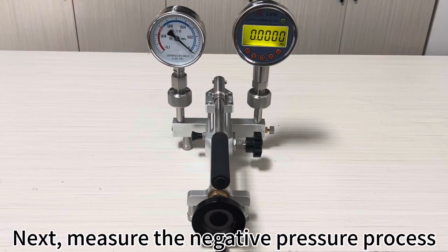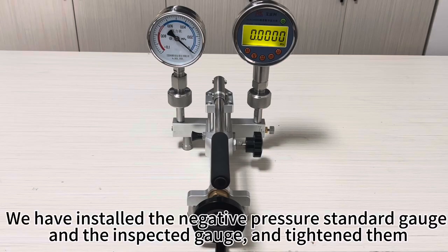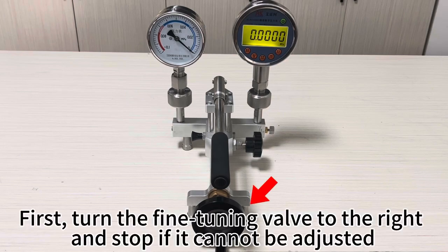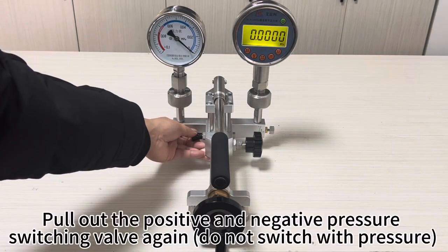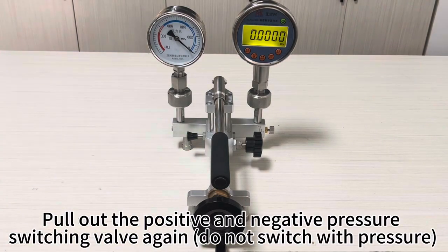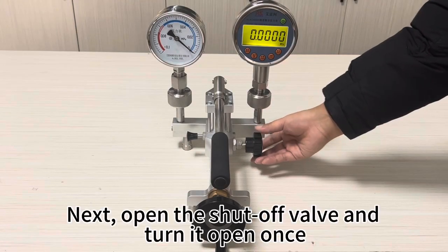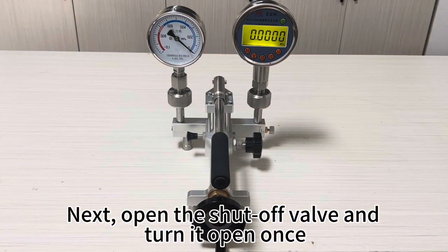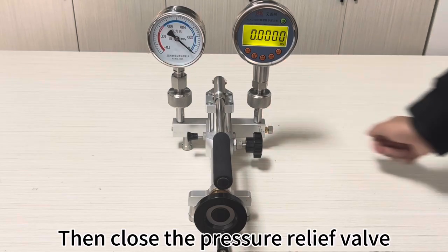Next, the negative pressure process. We have installed the negative pressure standard gauge and the inspected gauge and tightened them. First, turn the fine-tuning valve to the right and stop when it cannot be adjusted. Pull out the positive and negative pressure switching valve. Do not switch with pressure. Next, open the shut-off valve and turn it open once. Then close the pressure relief valve.